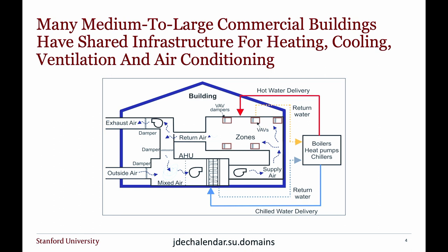The heating and cooling is passed on to the air. The cooling is passed on to the air in what's called the air handler, shown here, where air is cooled down by blowing it over coils of chilled water. It's then blown throughout the building through a central duct to different zones, which roughly correspond to rooms, in which little boxes, dampers, control the flow rate of air that goes through these zones. Some of the air is recirculated to the building, some is evacuated to the outside.